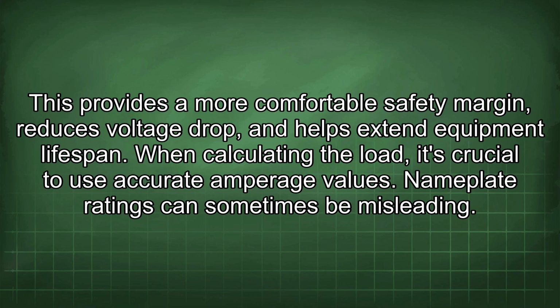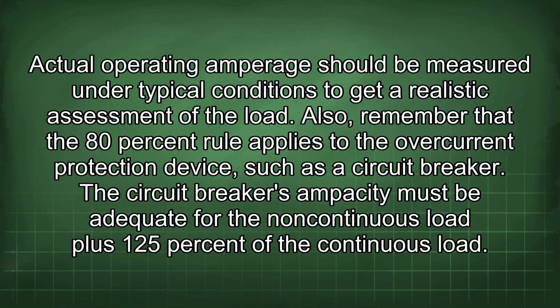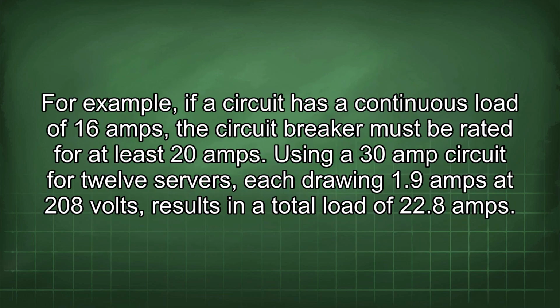When calculating the load, it's crucial to use accurate amperage values. Nameplate ratings can sometimes be misleading. Actual operating amperage should be measured under typical conditions to get a realistic assessment of the load. Also, remember that the 80% rule applies to the overcurrent protection device, such as a circuit breaker. The circuit breaker's ampacity must be adequate for the non-continuous load plus 125% of the continuous load.